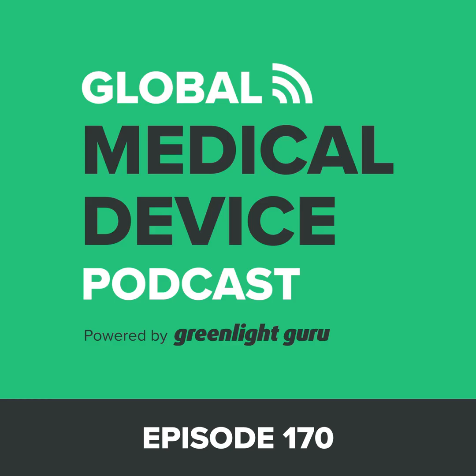And on that particular topic too, I would encourage folks, I was going to say I was going to be on the edge of my seat, but if that's the case, I would have been on the edge of my seat for about a year and a half now, but keep hearing that FDA is going to come out with some new guidances with respect to CSV, computer system validation, software validation, and Part 11 and all that sort of thing. That's not happened yet, but through the grapevine, what I've heard is FDA accepts as a practice to assess and evaluate what that software vendor might have already done with respect to V&V activities.